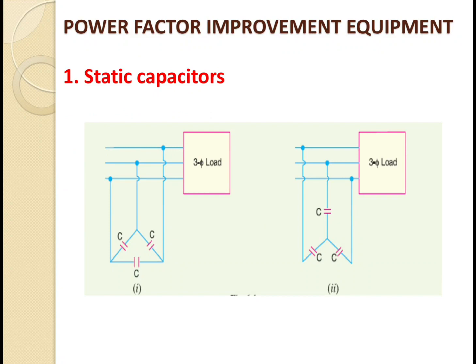Static Capacitors have advantages as well as disadvantages. The advantages of Static Capacitors are: first, they have low losses; second, they require little maintenance as there are no rotating parts; third, they can be easily installed as they are light and require no foundation; and last, they can work under ordinary atmospheric conditions.